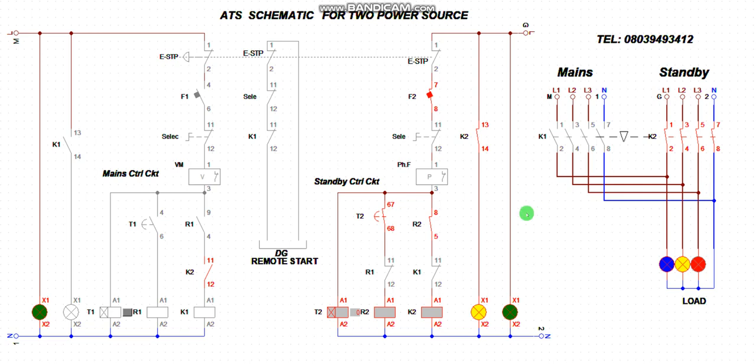Now, if this one is on now, you are using your genset and the national grid now restores power. Let me restore power here. Now, national grid is up. Now, this one will start counting 5 seconds again to stabilize the supply. So now look at it, now cut off. We cut off this mains and now take over, right? That is the function of this particular device design, okay?